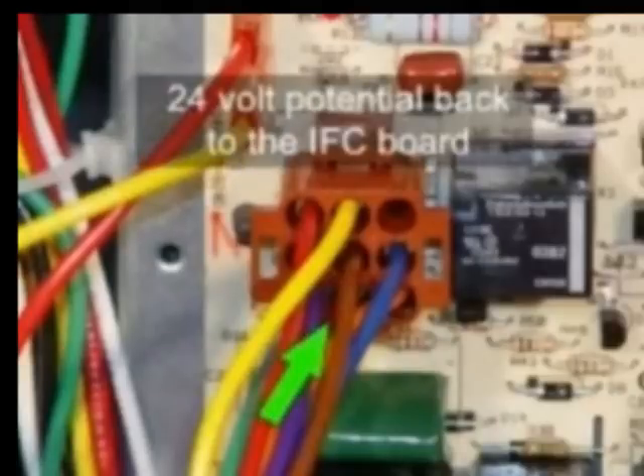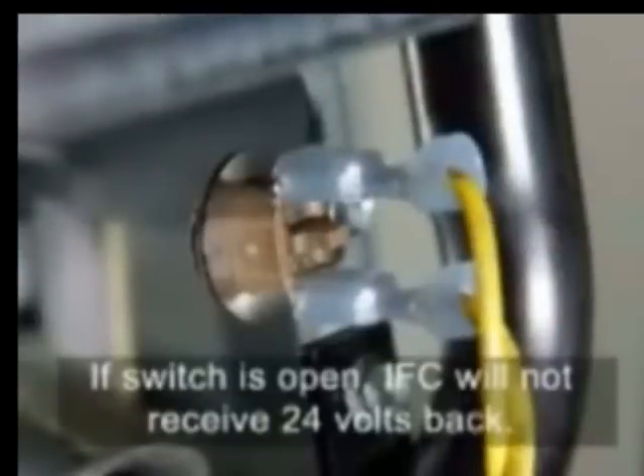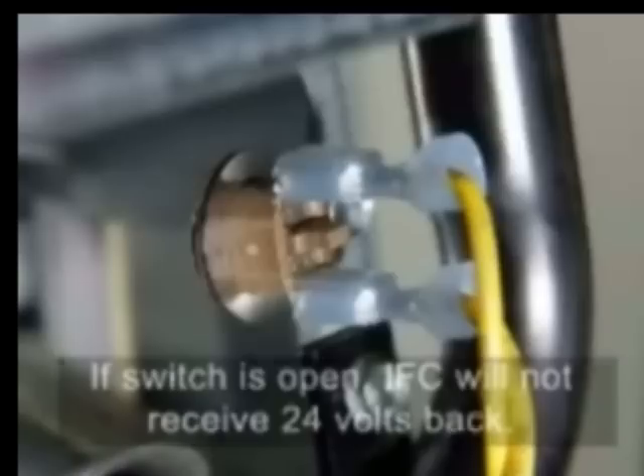When a call for heat is received by the IFC, the IFC sends 24 volts out to the flame rollout circuit. If the flame rollout circuit is open, the IFC will not receive 24 volts back.